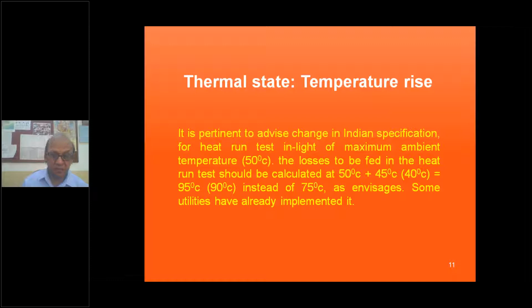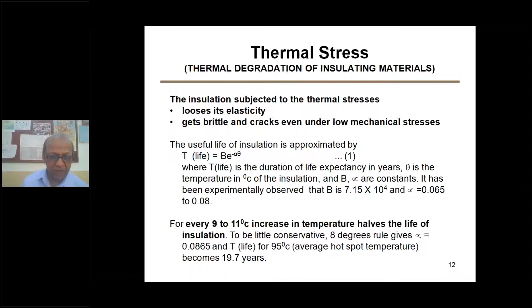So no doubt the insulation, as you may know, I am not taking much time on this particular slide, because insulation loses its elasticity, the tensile strength is gone, and it gets brittle and cracks even under low mechanical stress. No doubt mechanical stress ultimately causes the failure of insulation, which has already become very weak. And let's see the last particular para, where a 9 to 11 degree increase in temperature halves the life of the insulation. So it means consumption of life by an increase of 9 to 11 degrees becomes twice the normal rate. So that is the alarming situation regarding thermal stresses.